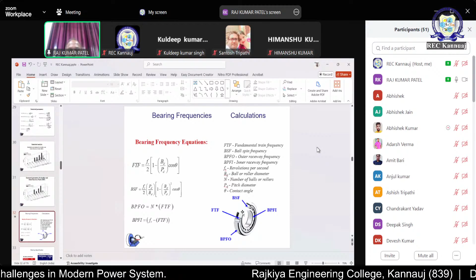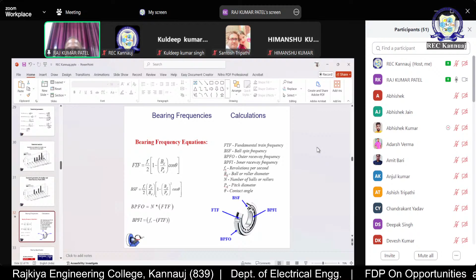BD is basically the ball or roller diameter—what size of ball is there, what is its diameter. N is the number of balls—how many balls are inside the bearing. PD is the pitch diameter of the bearing, and cos theta is the angle at which it contacts the inner race. These are the basic mathematical expressions.